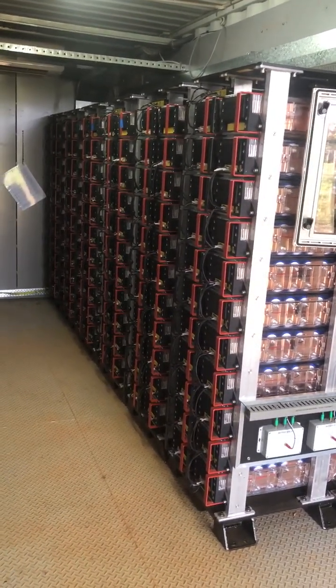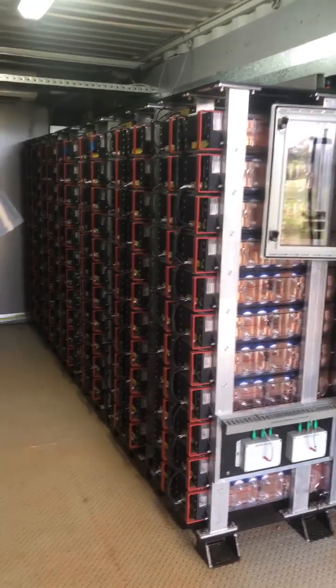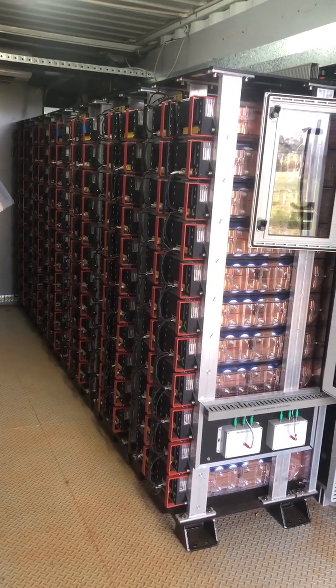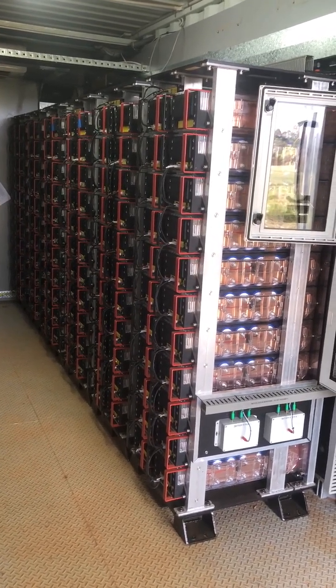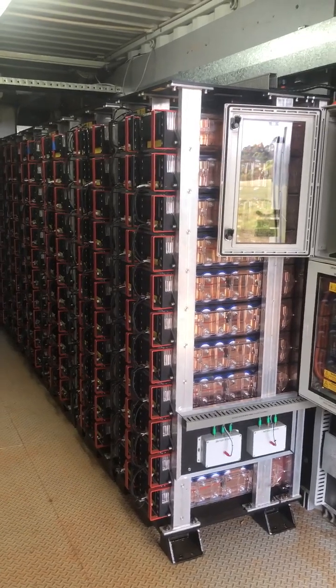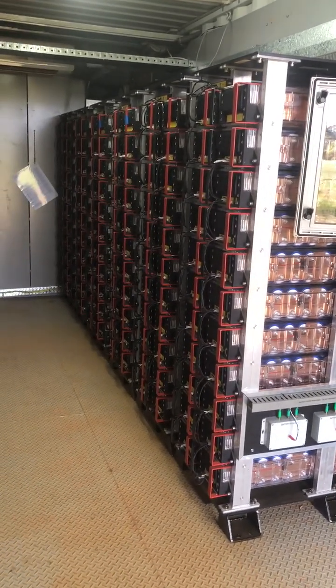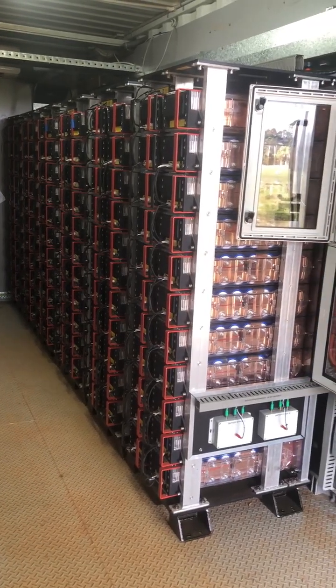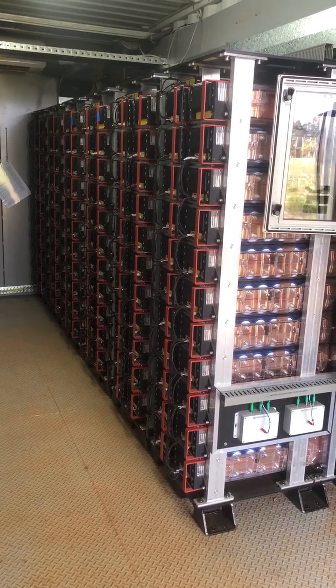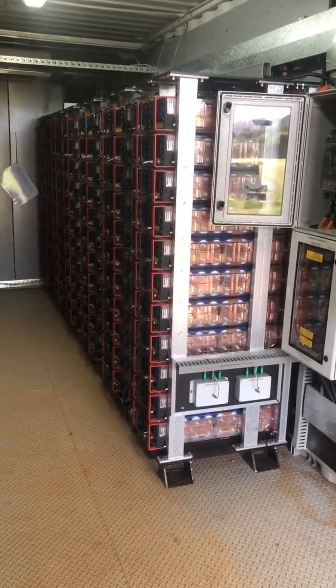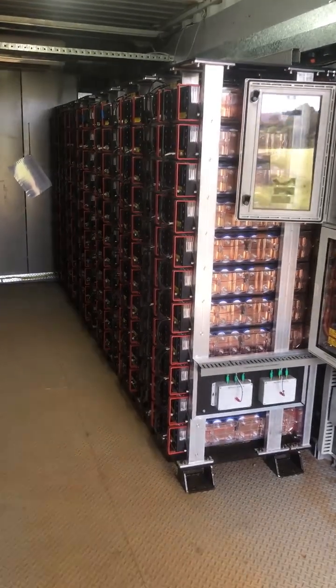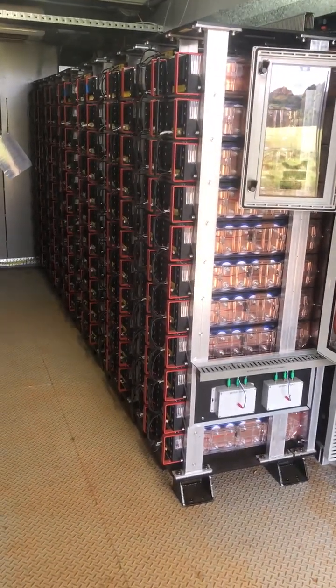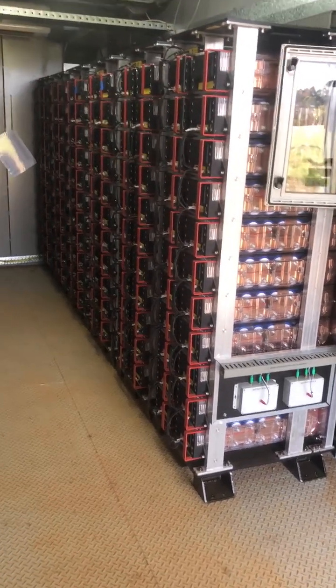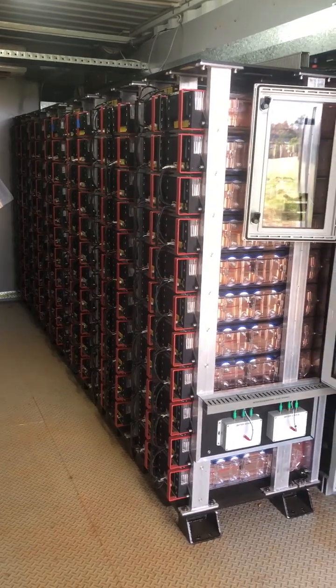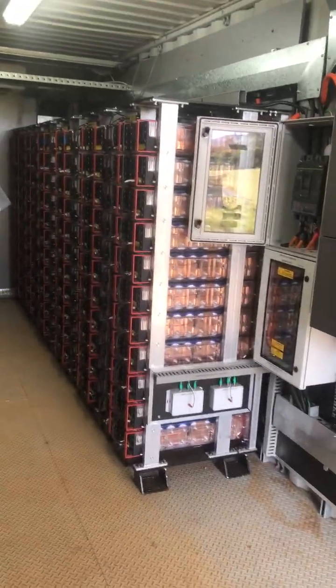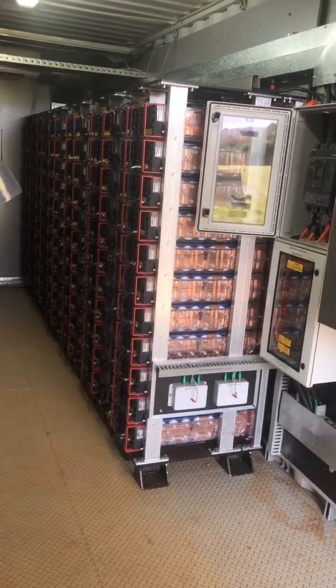And the major point of difference with these batteries is that we'll get 22,000 cycles out of a battery kit made of lithium titanate, but with battery kits made of lithium iron phosphate that you're probably more familiar with, you get somewhere between 5,000 and 7,500 cycles. So there's a significant difference with these batteries. However, they are significantly more expensive. The biggest advantage is, though, at 22,000 cycles, if you multiply the cost of the batteries over the cycles, you'll find that they're very economical batteries. However, the upfront costs are very high.